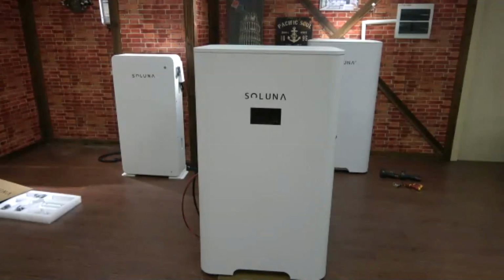The only thing is, if the grid is shut down and you only use the battery to supply your house, there's a surge power tolerance for the system, like the air conditioning type surge you mentioned. If the surge is within our spec, it will also start your home appliance. If it's over that, we will not allow it to use that. So it's something like this.